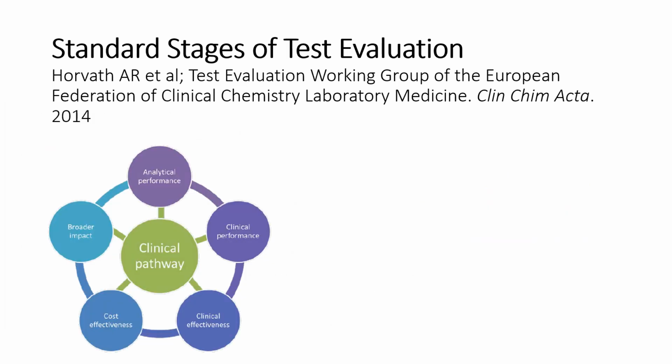When we think about evaluating tests, we tend to group studies in a sequence of doing analytical studies in the laboratory first, often on spiked samples or standardized samples, to estimate levels of detection and cross-reactivity and issues to do with false positives with other diseases. After that, we think about estimating test accuracy, clinical performance, and we may move on then in some circumstances to think about actually seeing whether tests lead to patient benefit.